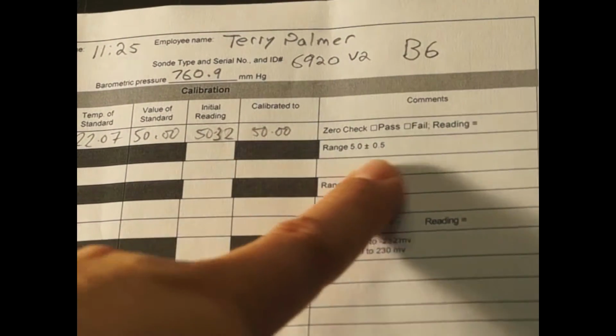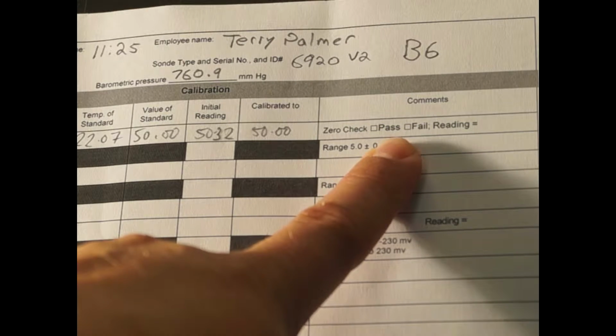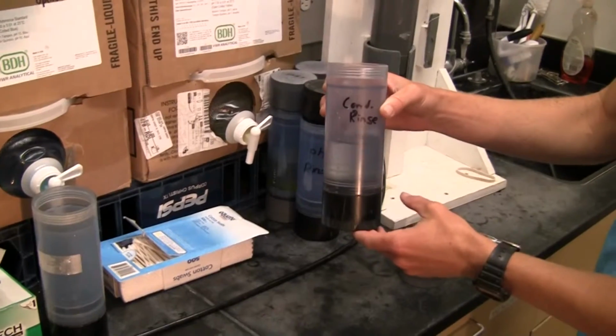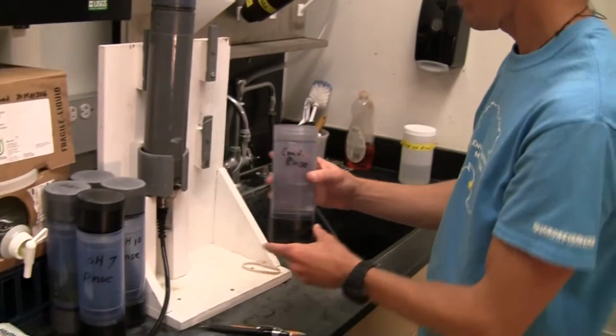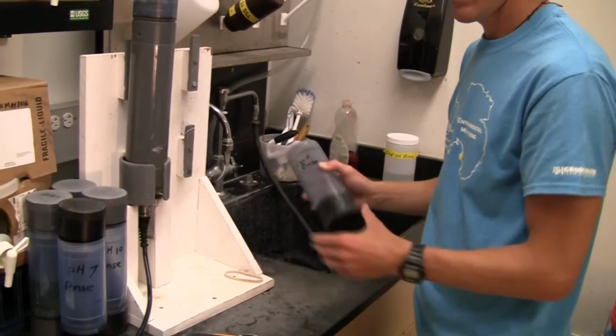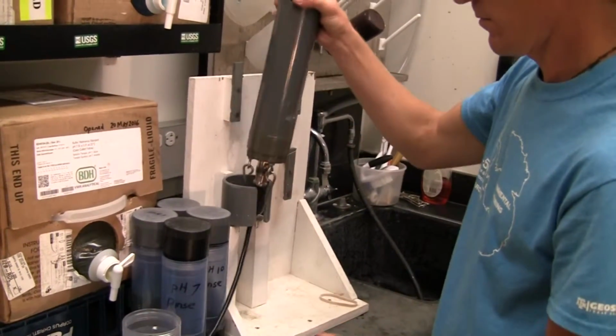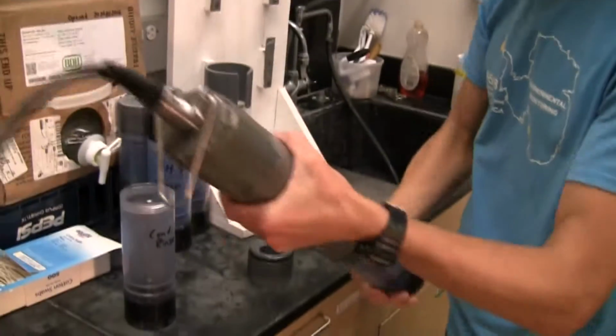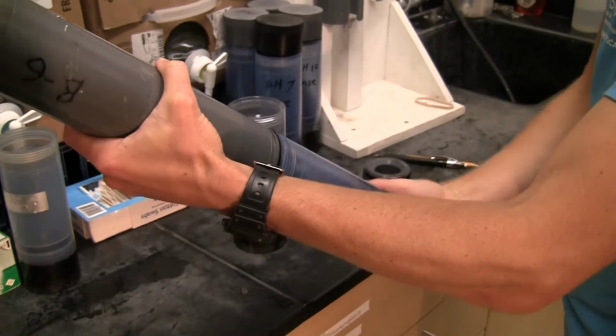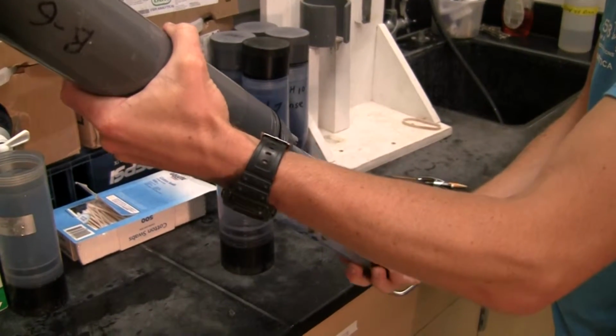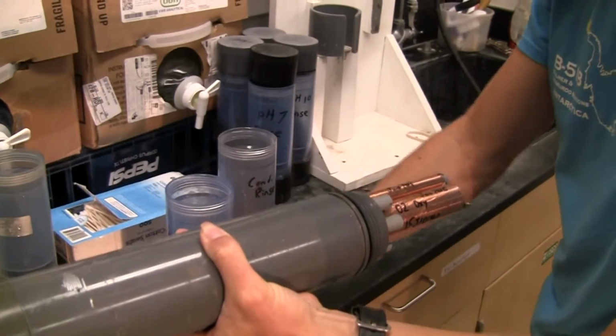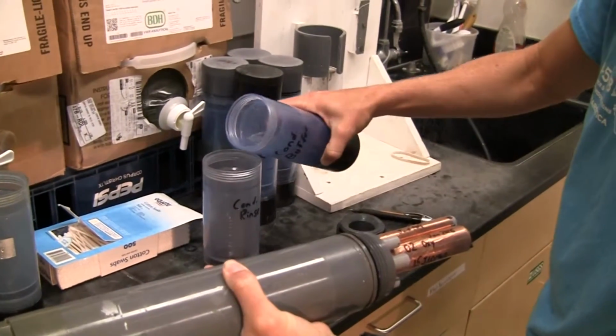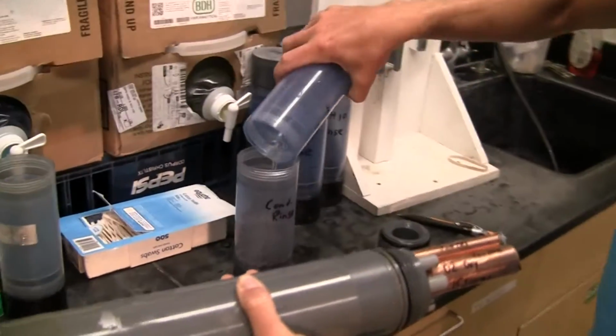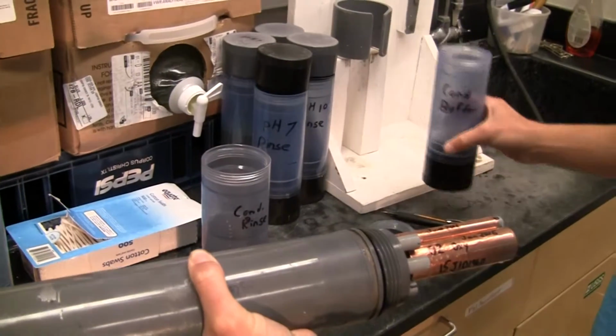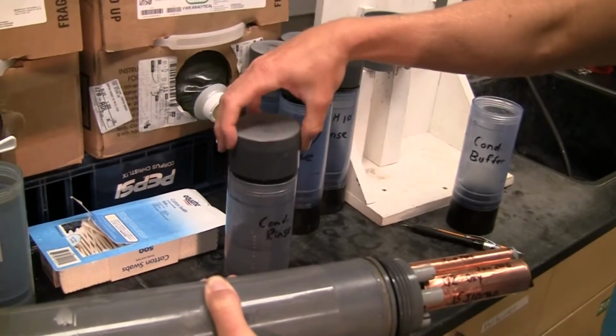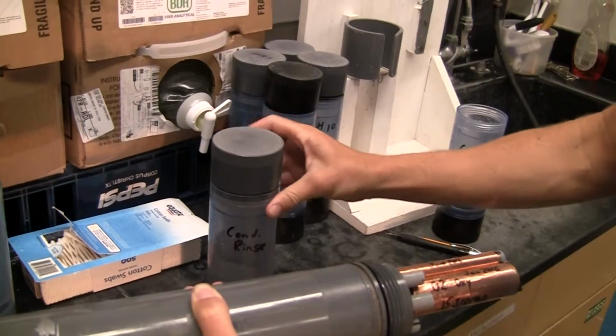Now there's a couple extra things we need to do. One is called the zero check, which we'll do right now, and we need to clean up our standards. So here we have our rinse bottle, and the rinse bottle needs to get poured into the sink. And remove the Sonde from the stand. And open the buffer container. Now this buffer we will save for the next time's rinse. So we pour back, we place the cap of the conductivity rinse on the bottle, and now we store back in the top of the shelf.